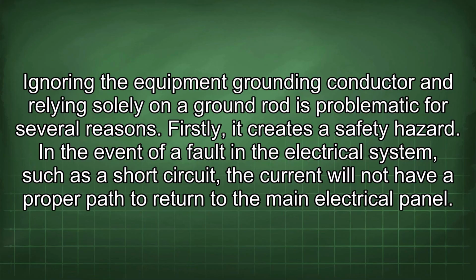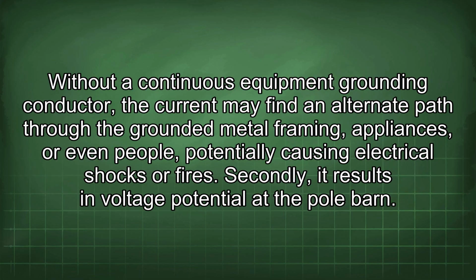Ignoring the equipment grounding conductor and relying solely on a ground rod is problematic for several reasons. Firstly, it creates a safety hazard. In the event of a fault in the electrical system, such as a short circuit, the current will not have a proper path to return to the main electrical panel. Without a continuous equipment grounding conductor, the current may find an alternate path through the grounded metal framing, appliances, or even people, potentially causing electrical shocks or fires.